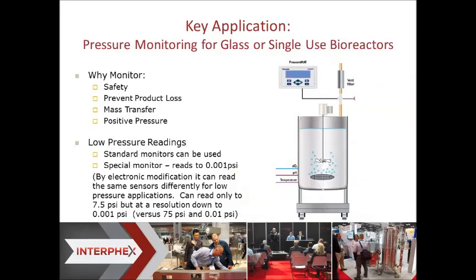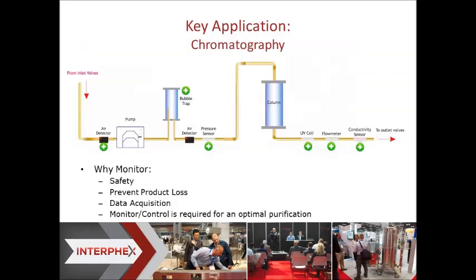In bioreactors, the single-use sensor is used to measure pressure to prevent any product loss, to facilitate mass transfer calculations, and more recently we came out with a new monitor, which a lot of these bioreactors can only take about 1 psi, where the same sensor can be measured down to 0.001 psi, so it's giving people a much more meaningful measurement. In chromatography, single-use sensors are critical to monitor and control for an optimal purification.